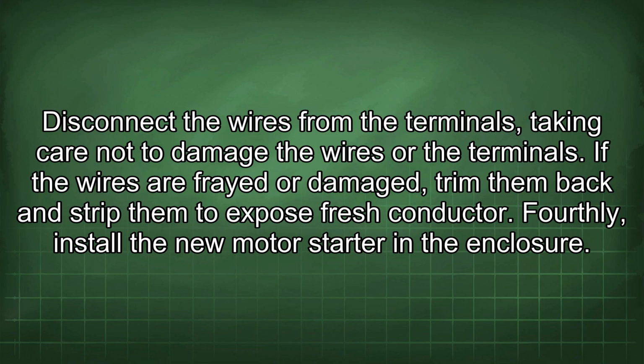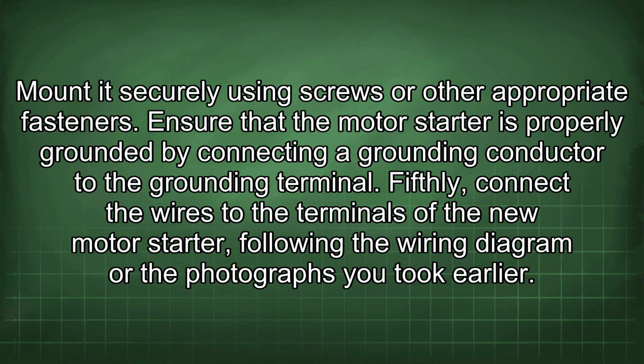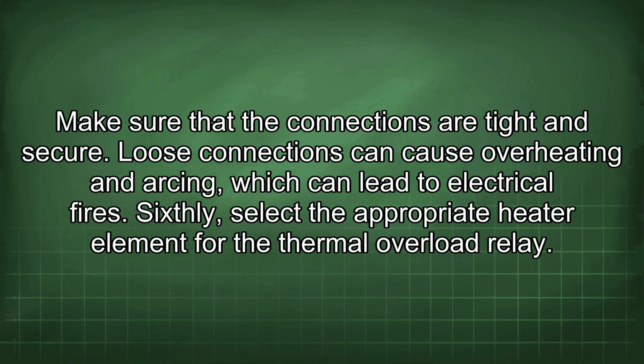Fourthly, install the new motor starter in the enclosure. Mount it securely using screws or other appropriate fasteners. Ensure that the motor starter is properly grounded by connecting a grounding conductor to the grounding terminal. Fifthly, connect the wires to the terminals of the new motor starter following the wiring diagram or the photographs you took earlier. Make sure that the connections are tight and secure. Loose connections can cause overheating and arcing, which can lead to electrical fires.